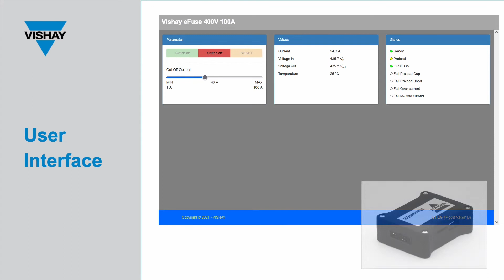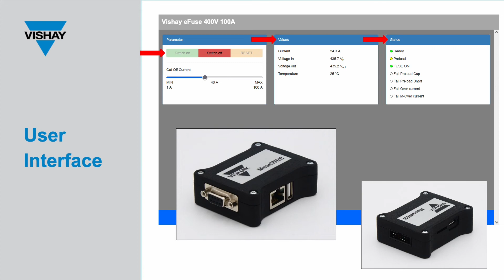To use the web interface, an external controller, which was also developed by Vishay and shown in these pictures, must be connected to the eFuse along with the external power supply I described a few minutes ago. Then a standard LAN cable is used to make the connection between the external controller and a computer. The web interface is divided into 3 sections. In the left column, the eFuse can be switched on and off, errors can be acknowledged and reset, and the maximum current can be set. In the middle column, the currently measured values of the eFuse are displayed: the input voltage, output voltage, load current, and ambient temperature. The right column displays the same status indicators as the LEDs on the PCB.